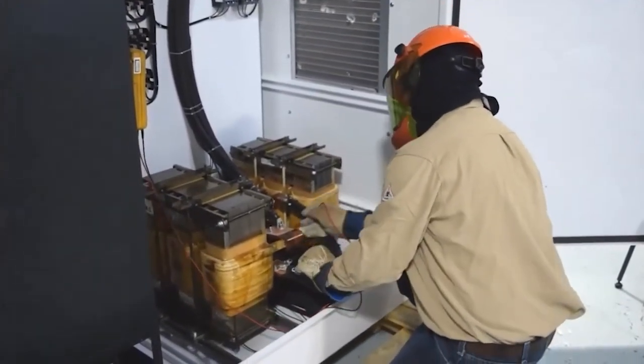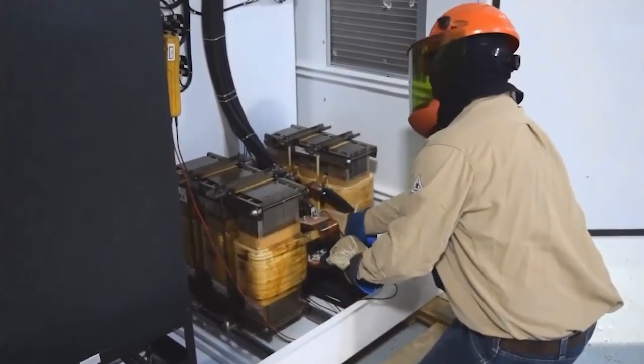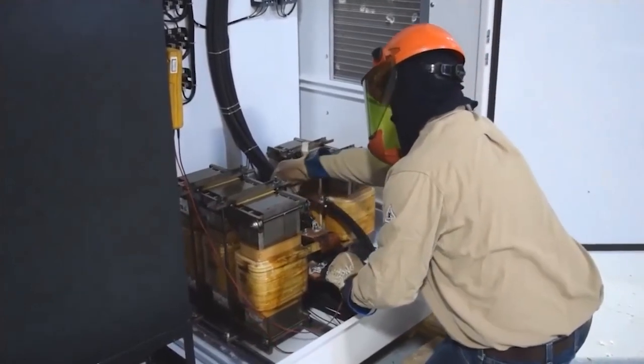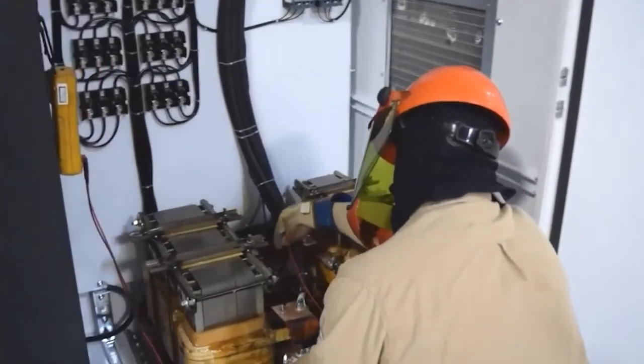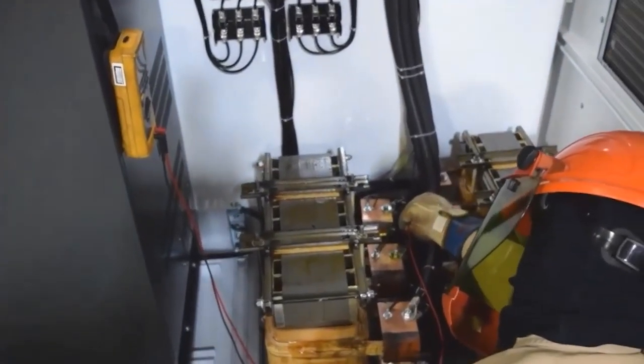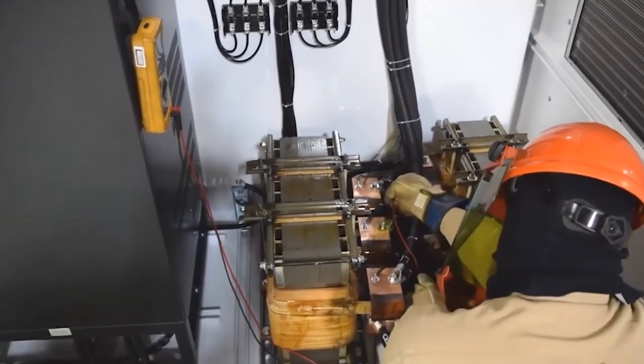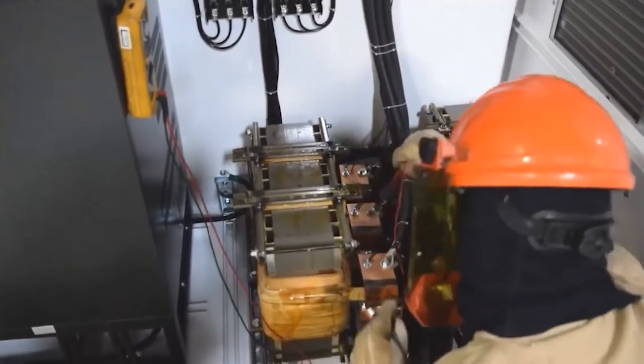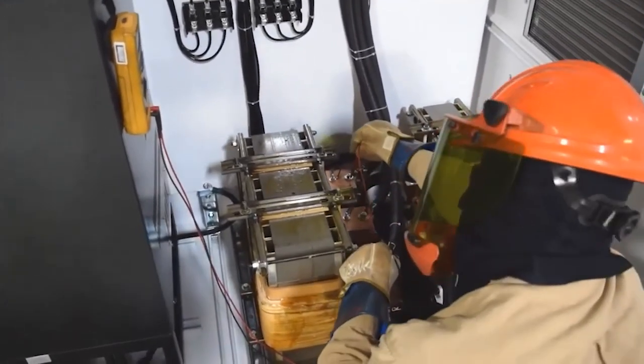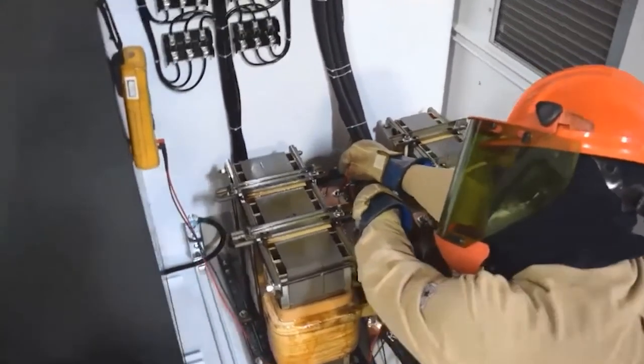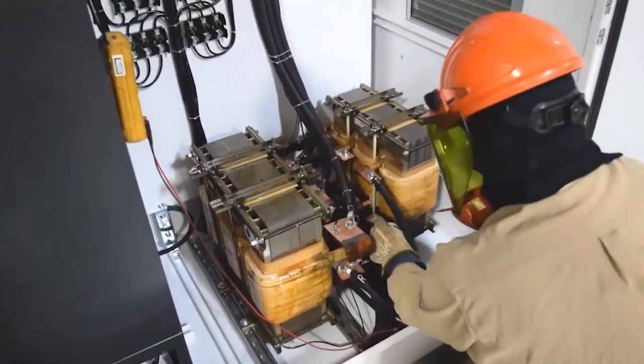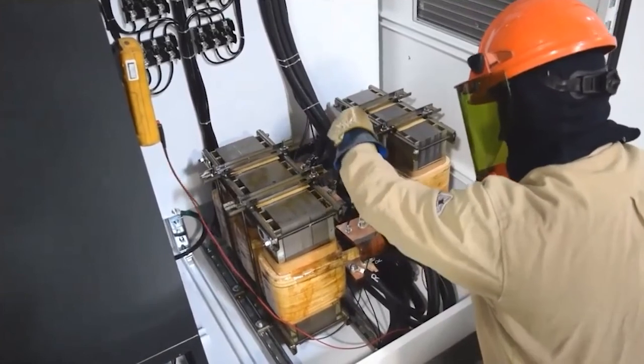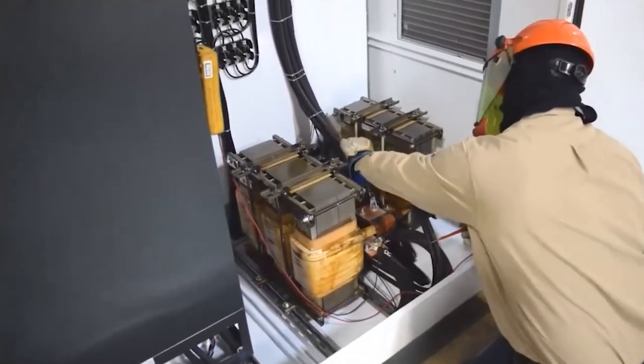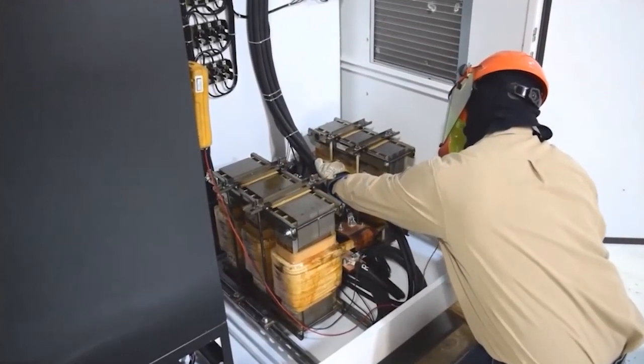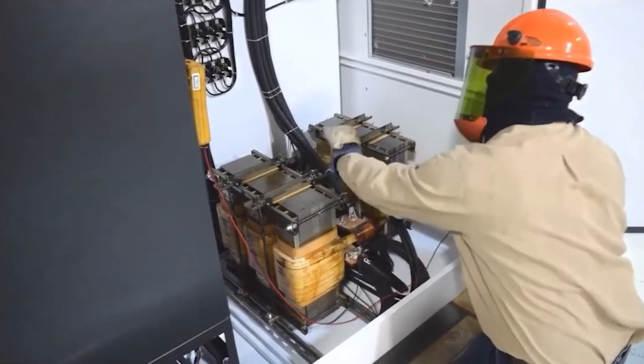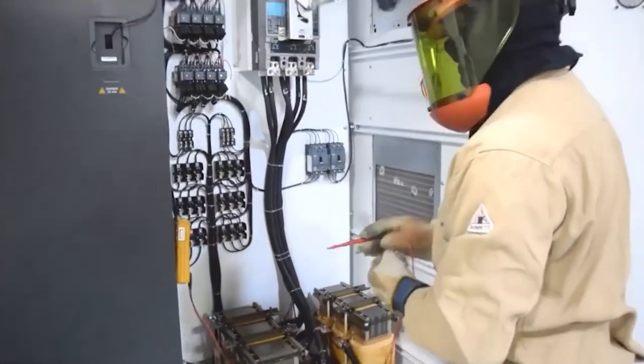All right, so now I'm going to get in position. I'm going to measure my reactors, my line reactors, and my tune reactors. Verify that I got proper voltages moving through them. In this case, your line is going to be the same as what your incoming is. Your output of your line reactor is going to be similar to what your incoming is, maybe a little bit less. And then your tune reactor secondary might be just a little bit higher. So let's say you had a 480 volt system. You're going to see something similar to that coming out of the reactor. And then on the tune reactor, you're going to see something that's probably in the neighborhood, a few volts higher probably.